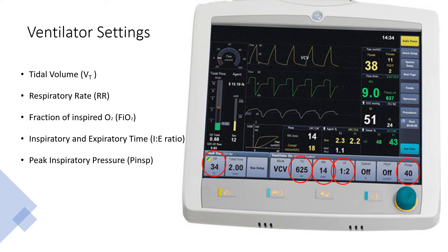If the inspired pressure reaches the preset limit, the inspired breath cuts out and expiration is allowed to occur. A rising PINSP may indicate reduced compliance in the lung. PEEP, or positive end-expiratory pressure, is the pressure in the alveolus at the end of expiration. It keeps the alveoli open at end expiration, increasing surface area primarily for oxygenation, and does not influence tidal volume so carbon dioxide clearance is not affected, though it does lead to increased inspired pressure.